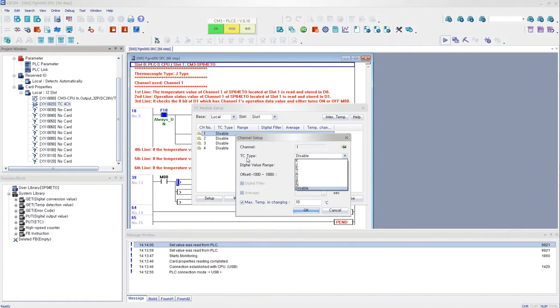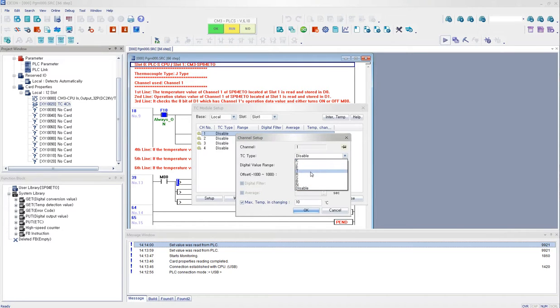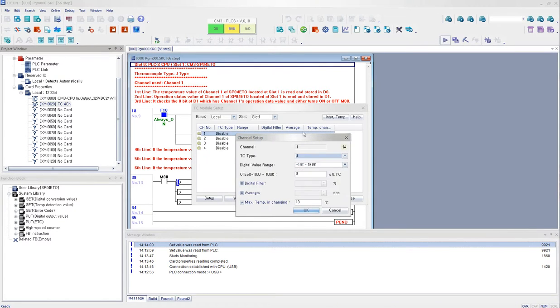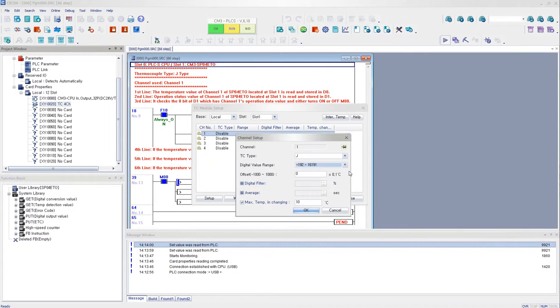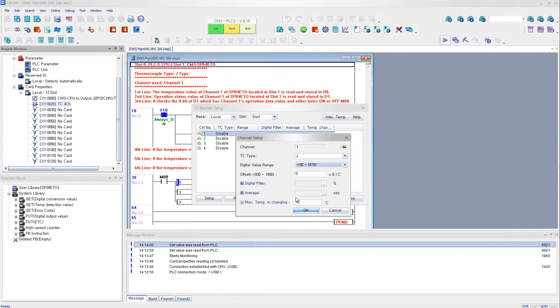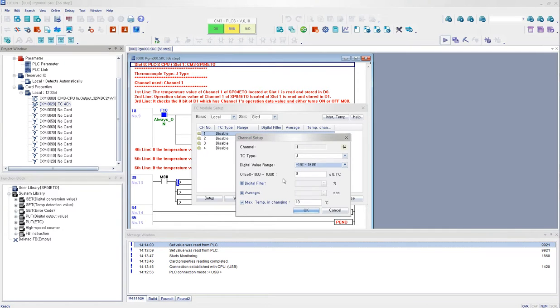And then I double click channel 1, and I select my TC type. It is available from K, J, E, T, R, S, B, and the N types. And for today's tutorial, I'm using the J type. And you can set up the digital value range. And today I'm going to stick with the default here. And I click OK. You can leave the rest of it. These configurations are not necessary.